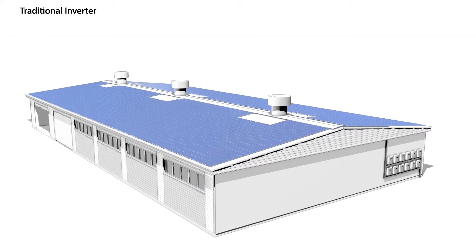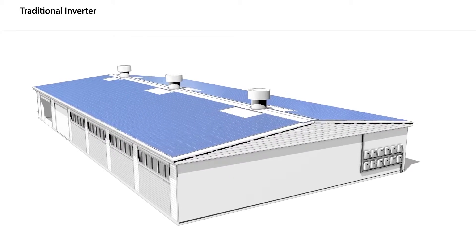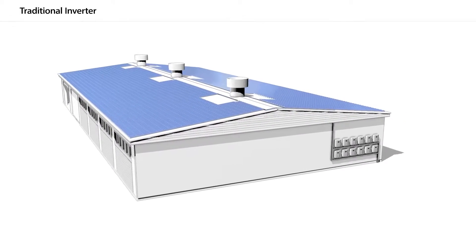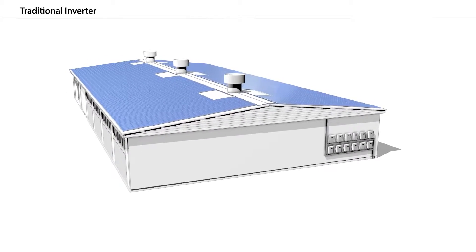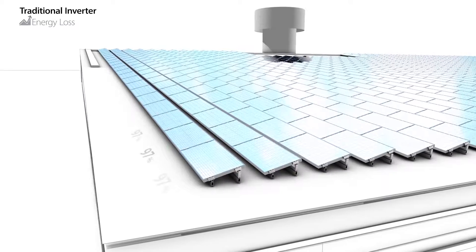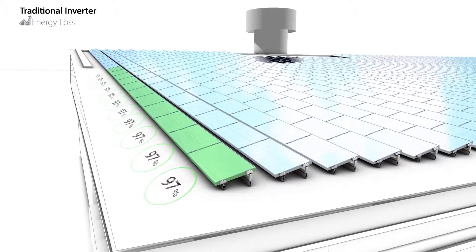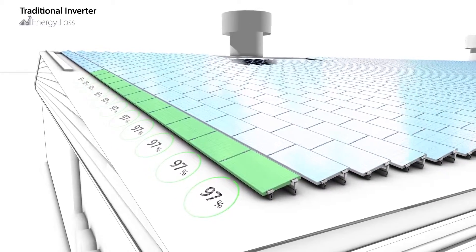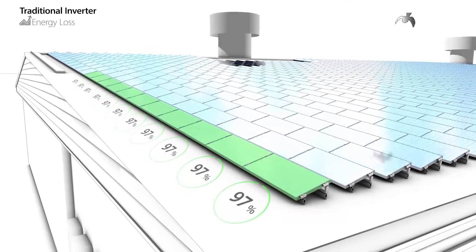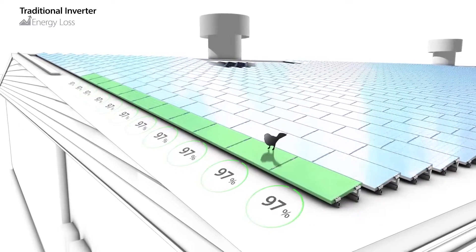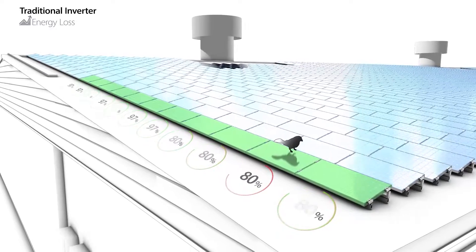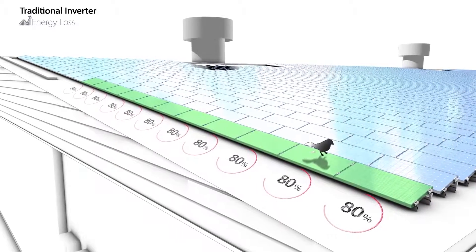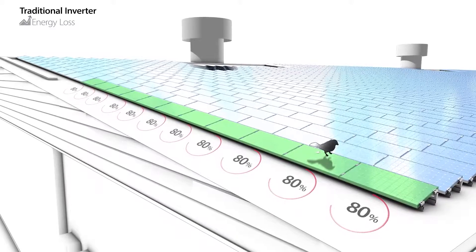Although traditional topology using string inverters is still used in the majority of large-scale installations, it suffers from a number of significant drawbacks. First, the system power output is limited. In traditional systems, panels are wired in series as a string. Each panel has its own power production profile, which is a function of its manufacturing variables, installation parameters, and shading patterns. This means that panels don't usually work at their maximum power point.